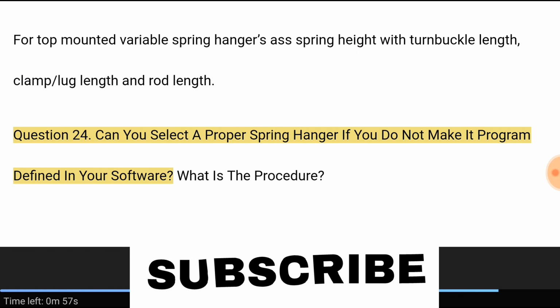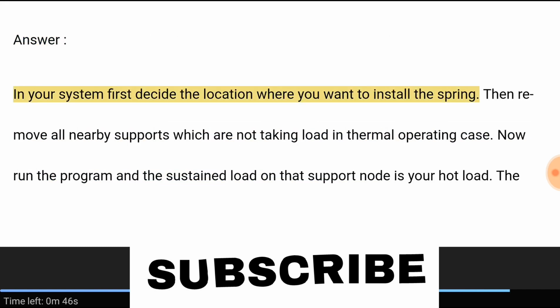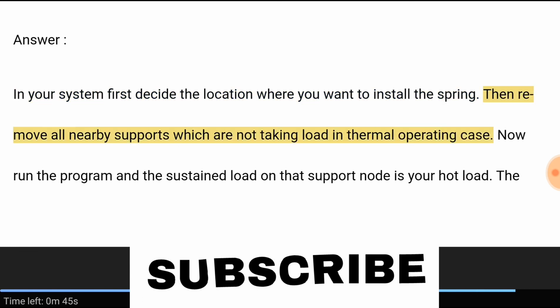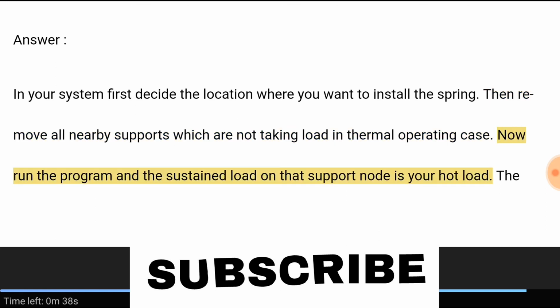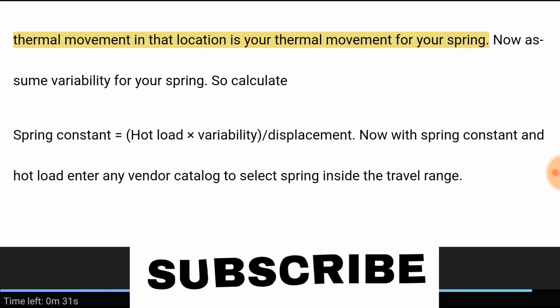Question 24. Can you select a proper spring hanger if you do not have it program-defined in your software? What is the procedure? Answer. In your system, first decide the location where you want to install the spring. Then remove all nearby supports which are not taking load in the thermal operating case. Now run the program and the sustained load on that support node is your hot load. The thermal movement in that location is your thermal movement for your spring.